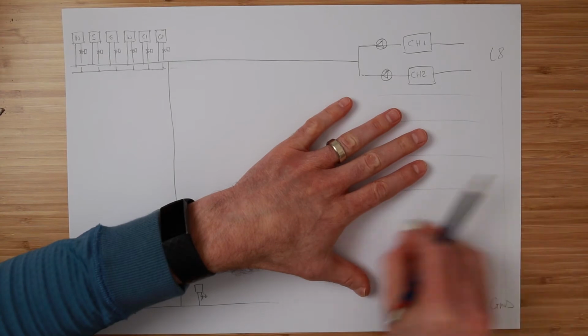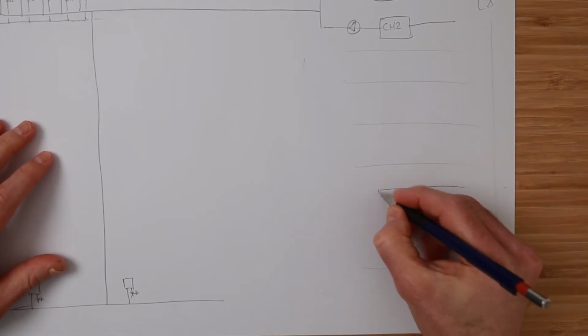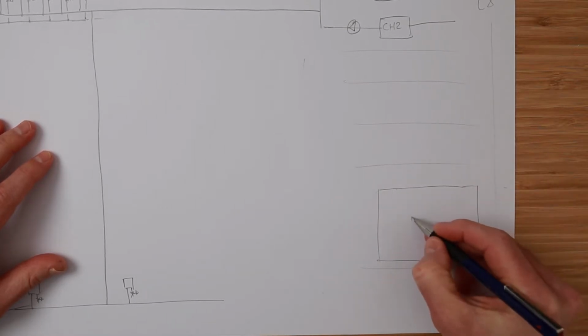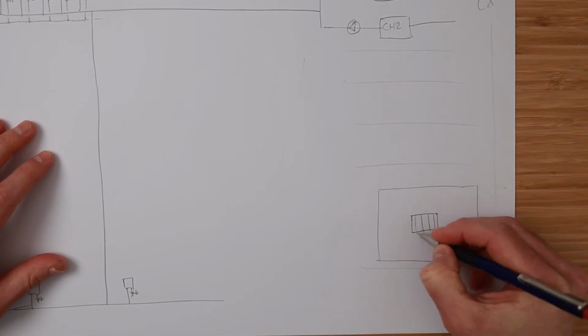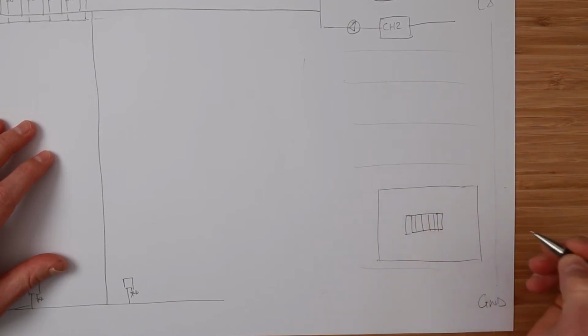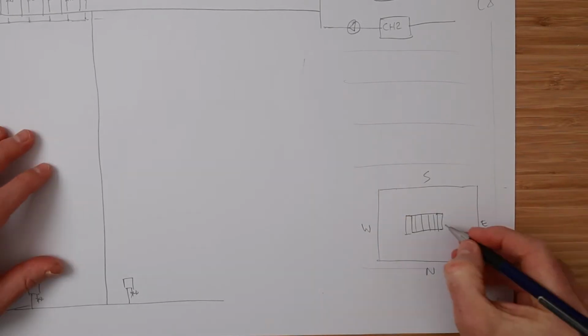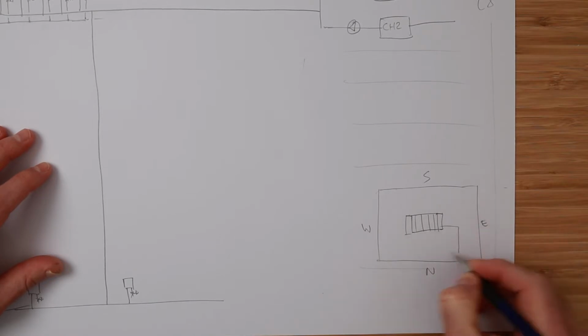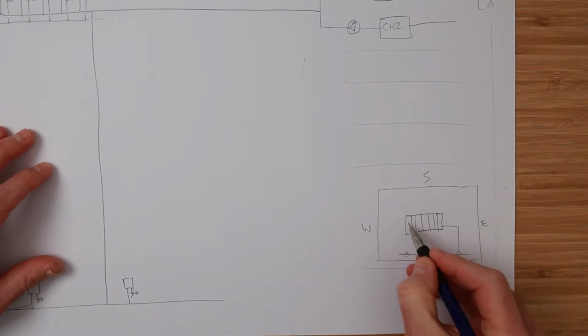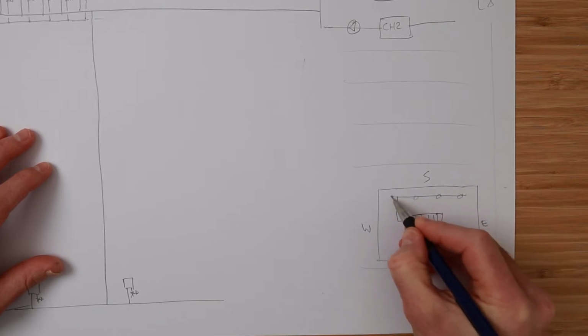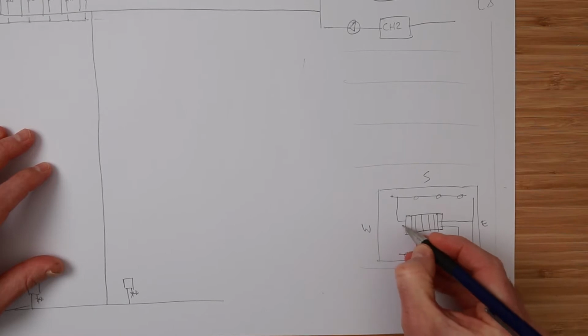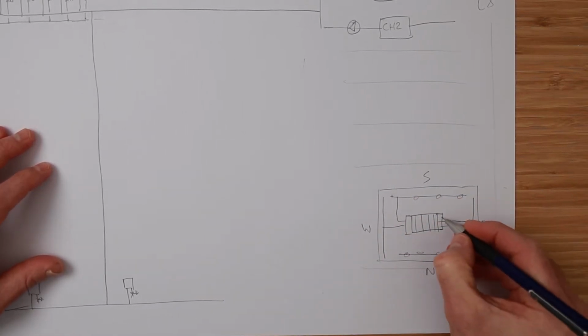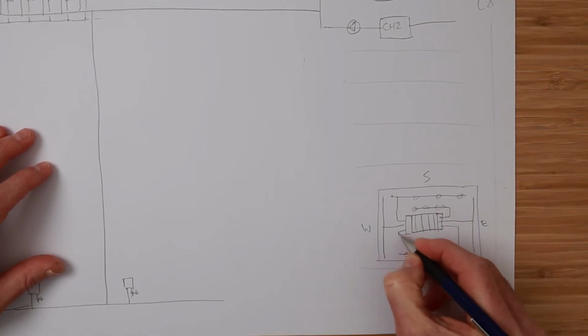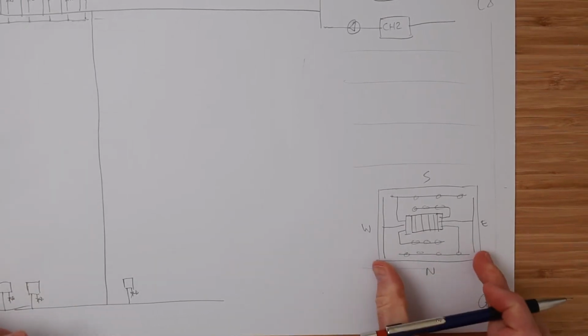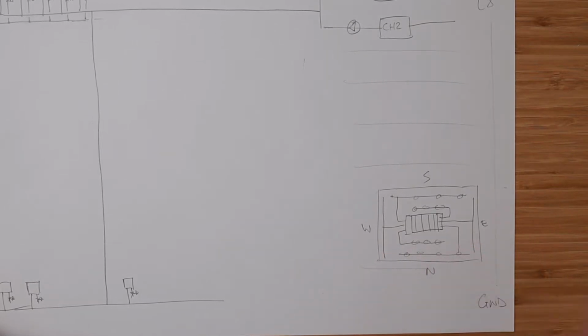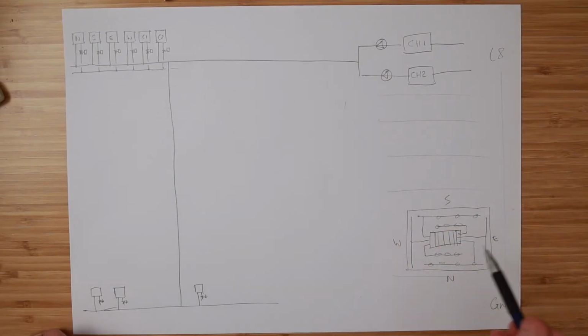So if we had a little drawing of the floor plan, this is a top view of the floor. In the middle here is the core of the building with the lifts and the toilets and all those sort of things. And on the end here we have our services risers. So north, south, east, west. So our north air handling unit would serve all the VAVs in the north. Our south air handling unit serves all the VAVs in the south. East air handling unit, west air handling unit, center zone 1, center zone 2. So across all 7 floors, each AHU does one of the 6 zones: north, south, east, west, center zone 1, center zone 2.